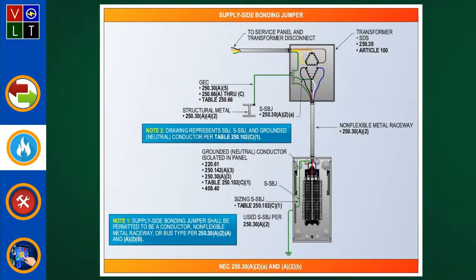Okay. All right. Now, this is a supply side bonding jumper in A2. The way we'll label this in a lot of ours, you'll see in the illustration, this is where I have a supply side bonding jumper going down to the panel board, and we label that as S-SBJ. Okay. We tell you here a supply side bonding jumper shall be installed with the circuit conductors from the source enclosure to the first disconnecting means where the source of a separately derived system and that first disconnecting means, which is at that panel board, are located in separate enclosures.